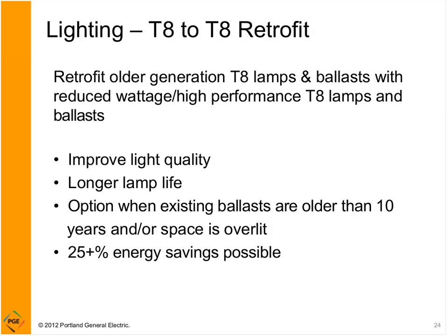the space is overlit. Sometimes I'll see a space, like an office space, for example, that is way overlit. Recommended light levels in offices are maybe 30 to 50 foot candles. I've seen 80, 90, 100 foot candles, just way more light than is really needed. So you can see a pretty significant reduction just in addressing the appropriate light levels. So 25% or more energy savings is possible with this type of upgrade.